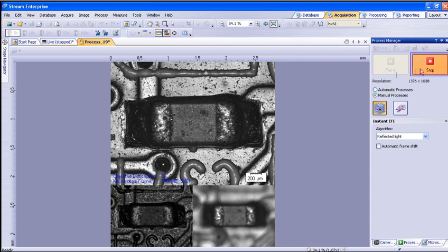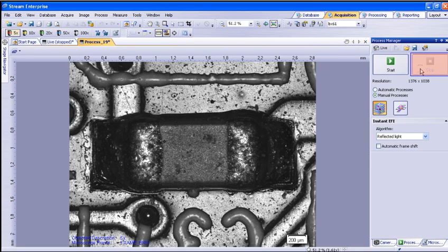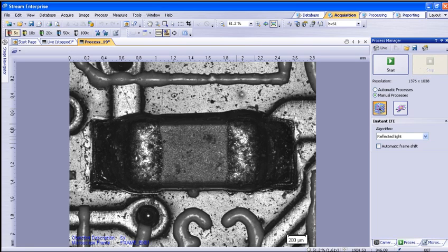Once you have scanned the focus from bottom level to top level, you will notice the focus map will be filled in showing your EFI is complete. You then need to click on the Stop button in the Process Manager tool window. The software will then display the completed EFI image or all-in-focus image as a new document.